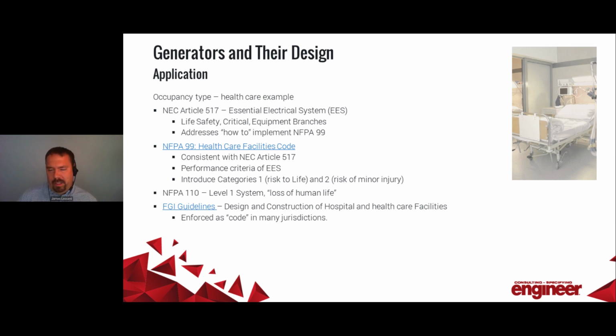So let's take an example here, a healthcare example. Again, NEC Article 517 governs the requirements for the electrical system in a hospital or other healthcare facility. Specifically, it introduces the essential electrical system, which requires three separate branches of distribution, the life safety, critical, and equipment branches, unique to healthcare installations. It also references, in many cases, NFPA 99. And so it is really the how to implement 99. It's kind of the instruction manual to follow to meet the 99 requirements.